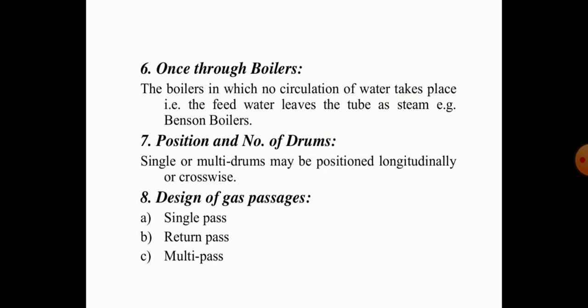Another type of steam generator is the once-through boiler. In this type, there is no circulation of water — the feed water flows through the tubes and steam is collected directly once generated. Benson invented this method for steam generation, so these boilers are also called Benson boilers.